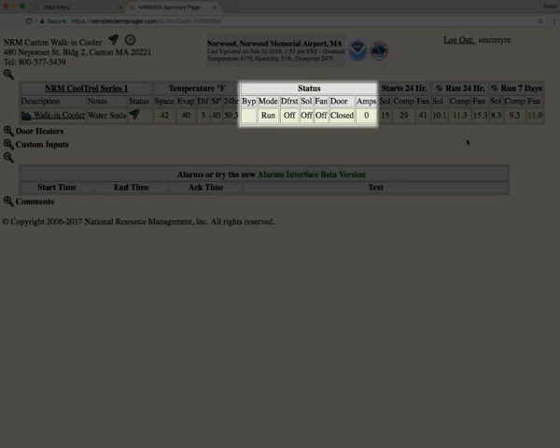Amp section, we have an amp meter or a current transducer that is put on the compressor itself to know if the compressor is actually running or not. So when our call for cooling is happening, there should be an amp draw. Right now, we're not calling for cooling and the compressor is off showing zero amps.